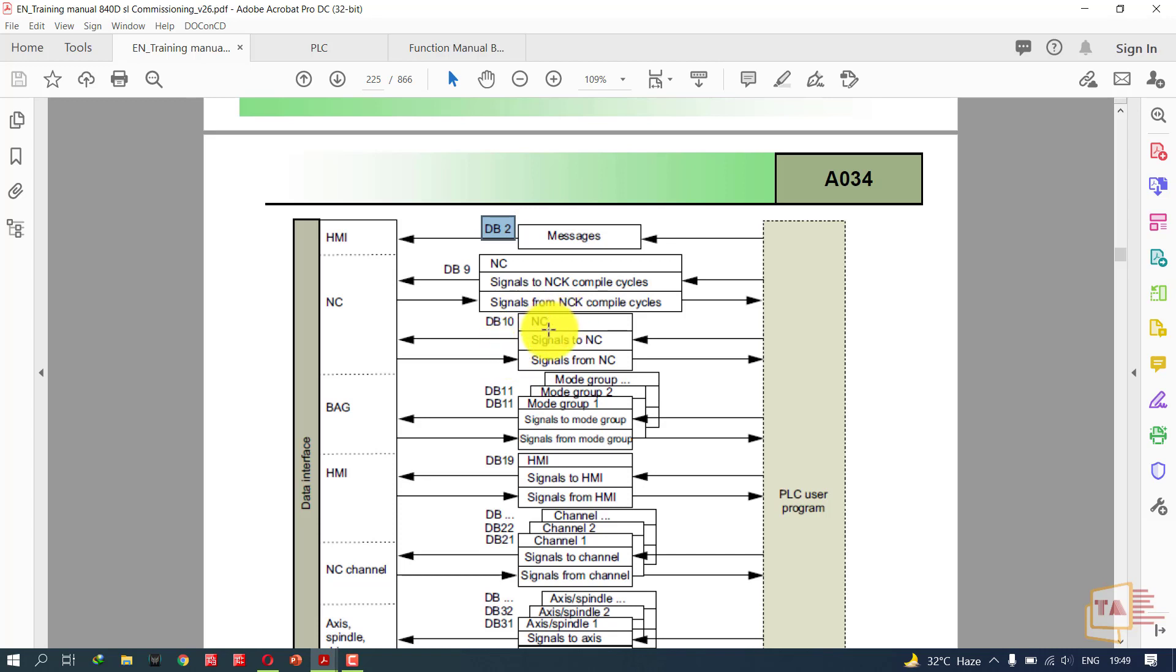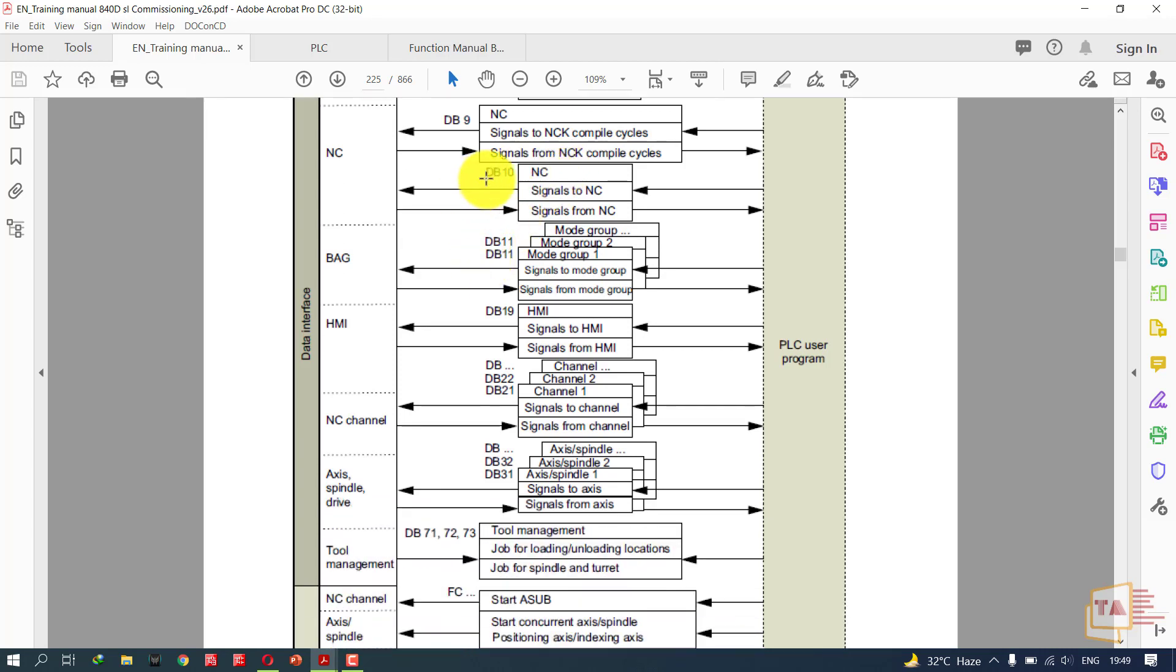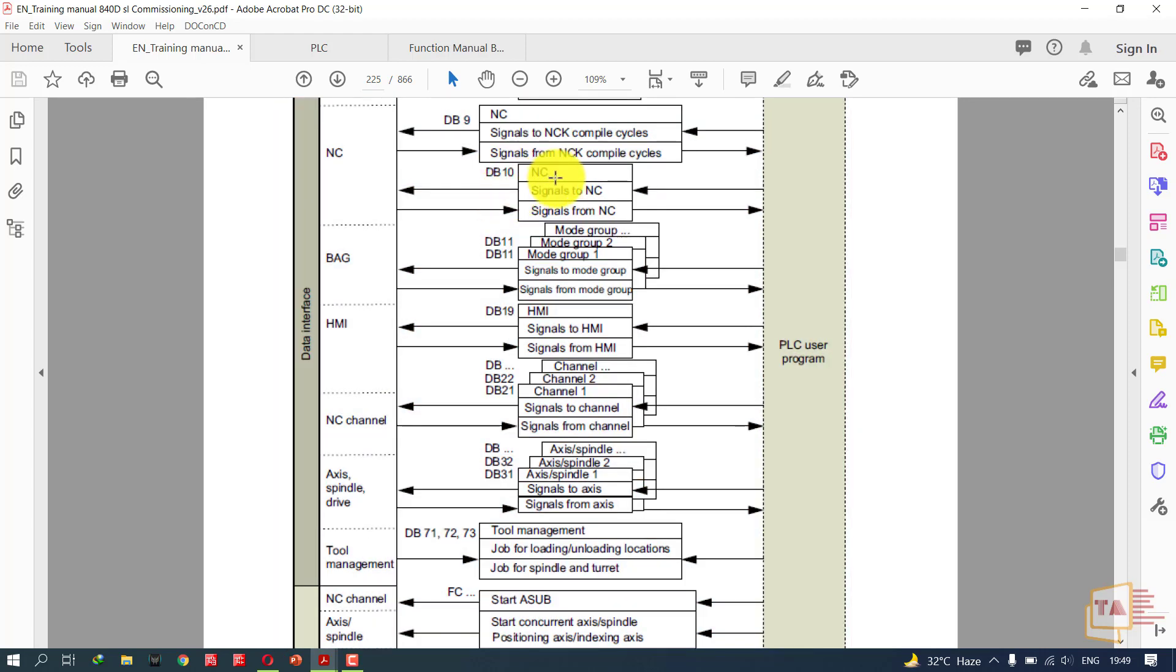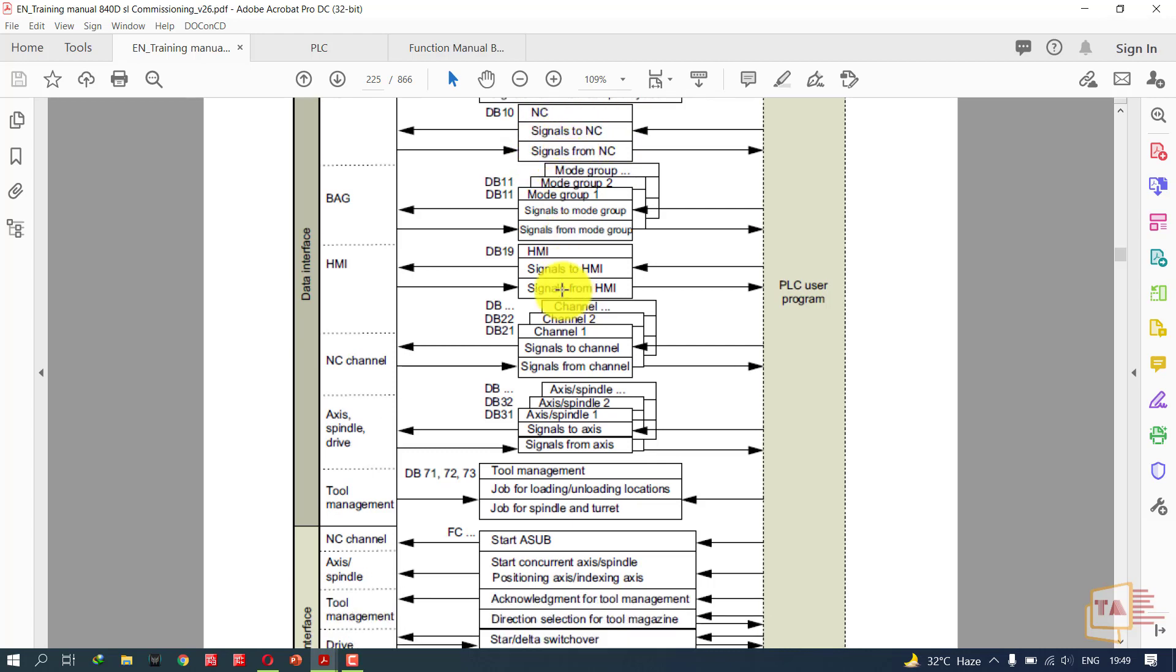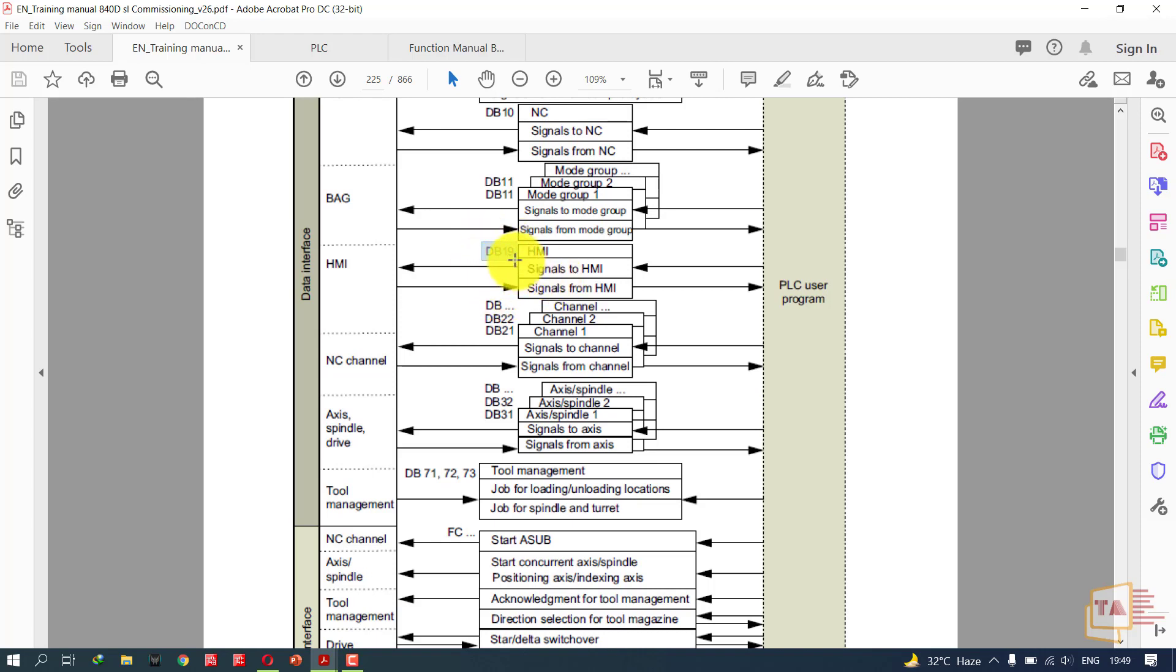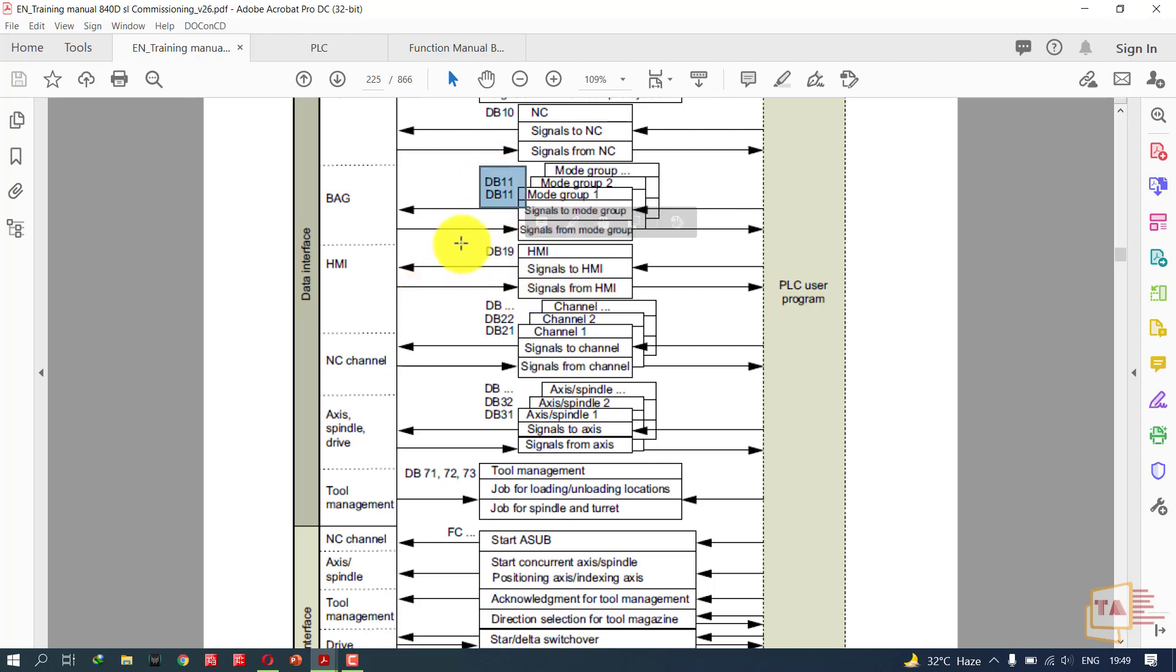We have DB10, which is particularly allocated for NC. In this DB10 we will be able to send signals to NC and receive signals from NC. Next is HMI. If you want to control HMI or send signals to HMI or receive signals from HMI, you should use DB19. For example, using DB19 you can influence the HMI signals. You cannot use DB11 for HMI signals because it is predefined.